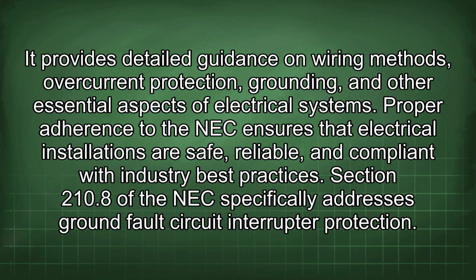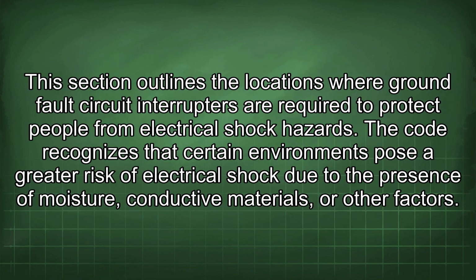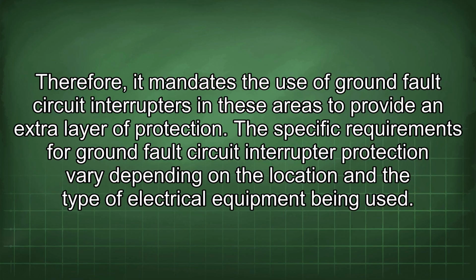Section 210.8 of the NEC specifically addresses ground fault circuit interrupter protection. This section outlines the locations where ground fault circuit interrupters are required to protect people from electrical shock hazards. The code recognizes that certain environments pose a greater risk of electrical shock due to the presence of moisture, conductive materials, or other factors. Therefore, it mandates the use of ground fault circuit interrupters in these areas to provide an extra layer of protection. The specific requirements for ground fault circuit interrupter protection vary depending on the location and the type of electrical equipment being used.